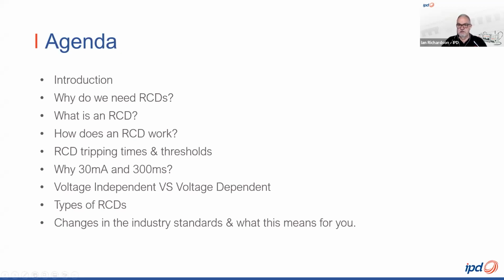We'll start off with the introduction, which we're doing right now, and then we'll lead into why do we actually need RCDs and what is an RCD. We'll then jump into a bit of old tech school work. How does an RCD work? And a little bit of information on the RCD tripping times and the threshold currents according to the standards. Also, why 30 milliamp and 300 millisecond has been chosen for protection of the people, and also what's the difference between voltage independent and voltage dependent RCDs and different types of RCDs, and what changes in the industry standard are happening, and what does it mean for you?